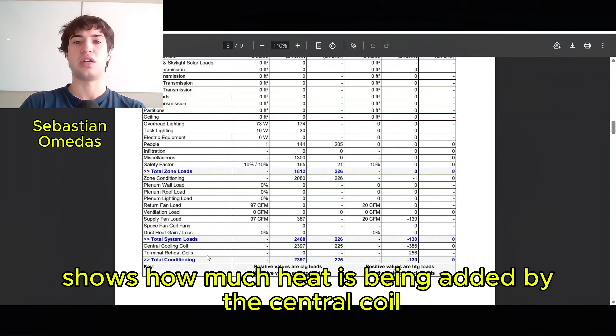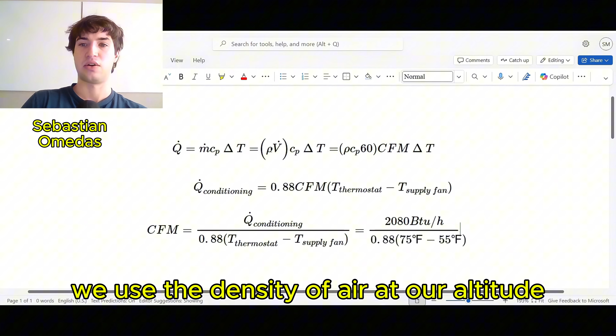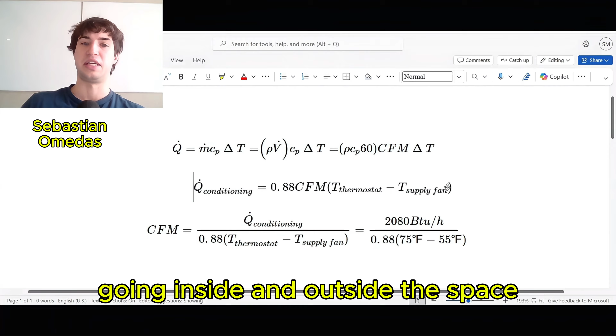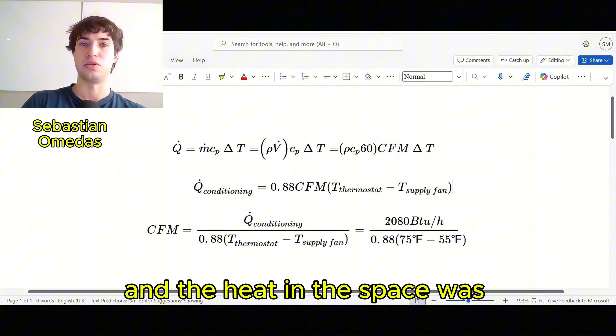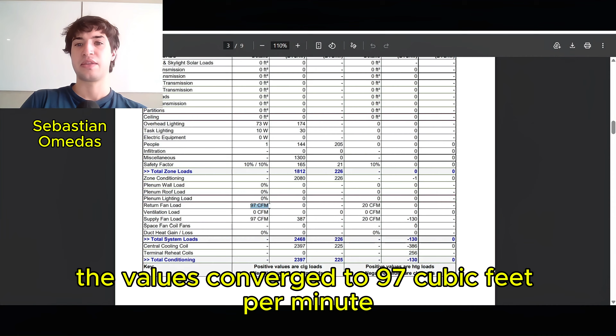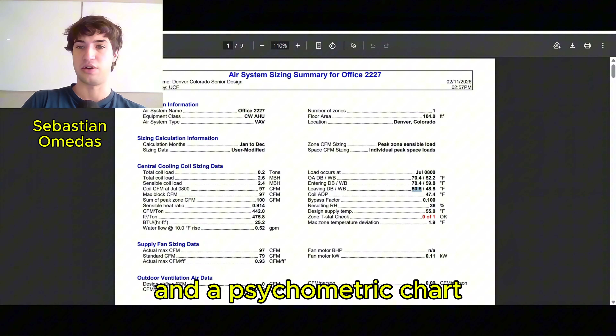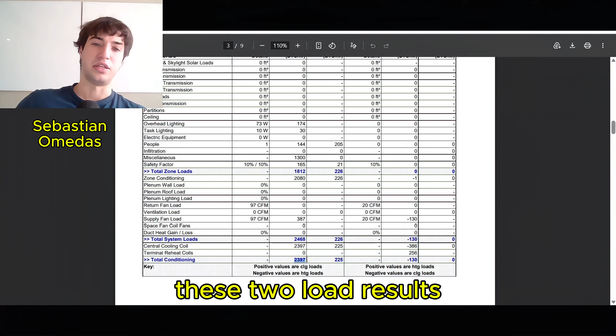The zone conditioning shows how much is being added by the central coil, which requires the heat equation. We use the density of air at our altitude and the heat capacity of air in a specific form that helps us proceed. We use the temperature of air going inside and outside the space. We use the thermostat temperature as an initial guess, and the heat in the space was 2080 BTU per hour. The values converge to 97 cubic feet per minute and 78.4 Fahrenheit. Then another loop is done with an initial guess near the saturation line and a psychrometric chart. The final values converge to 50.5 Fahrenheit and 2397 BTU per hour. These two load results help the team create the schedule and move on with the HVAC installation choices.